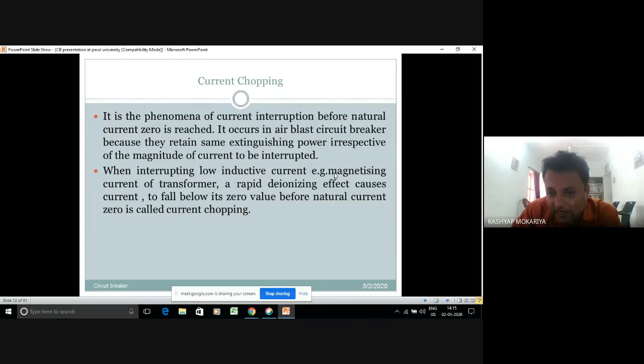When interrupting a low inductive current, such as the magnetizing current of a transformer, a rapid deionization effect causes the current to fall below its zero value before the natural current zero. This is basically known as current chopping. Now, where do you find this air blast circuit breaker?